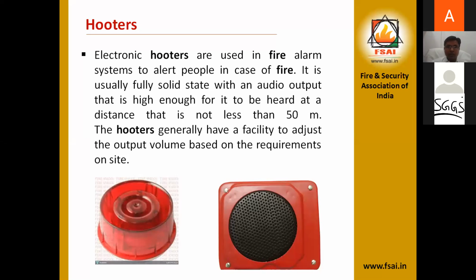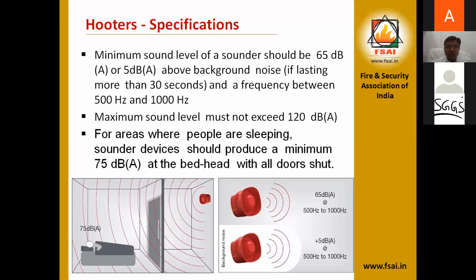What are the hooter specifications? These are very important design concepts. The minimum sound level of a sounder should be 65 decibels or 5 decibels above background noise. It means if the background noise is 70 decibels, it should be 70 plus 5, that is 75 decibels, lasting for more than 30 seconds, and a frequency between 500 Hz and 1000 Hz. The maximum sound level must not exceed 120 decibels. The minimum is 65 decibels and the maximum is 120 decibels, so the sound remains within this range. For the areas where people are sleeping, as you can observe in this figure, sounder devices should produce a minimum of 75 decibels at the bed head with all doors shut. So we have the chance to arrange the frequency of the hooter as per the requirement and the site condition.